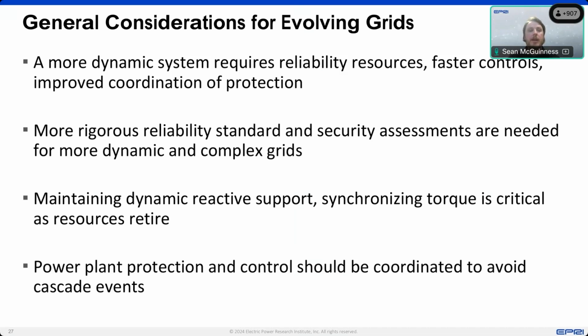Many grids already focus on ensuring that transmission line protection has loadability limits and power swing blocking, so that it doesn't respond to power swings. But also in our power plants, we need to ensure that voltage and frequency protection is coordinated to avoid triggering these types of cascade events. So that's essentially a summary of where we are right now and our understanding of it, based on the available data.